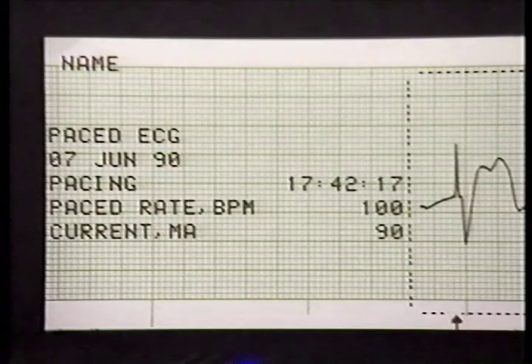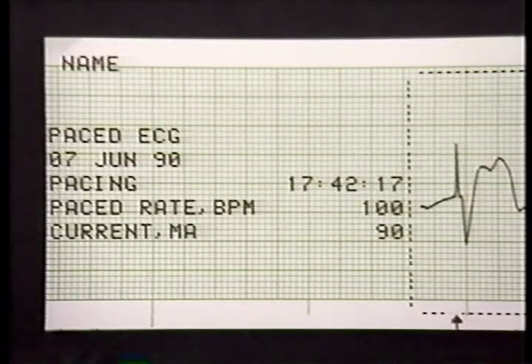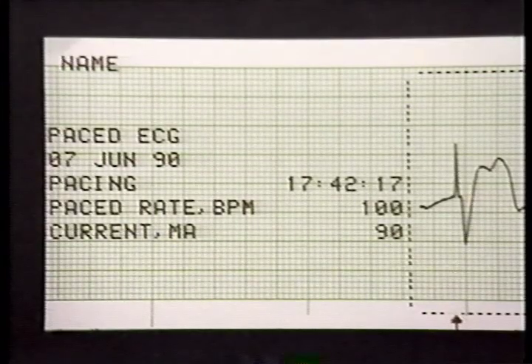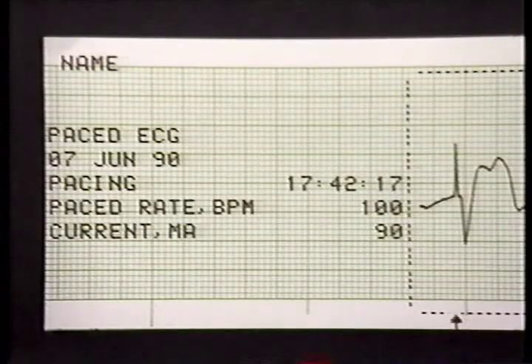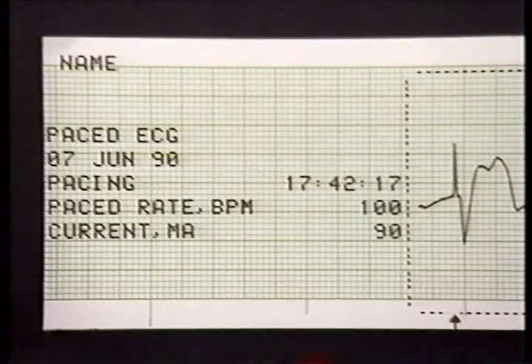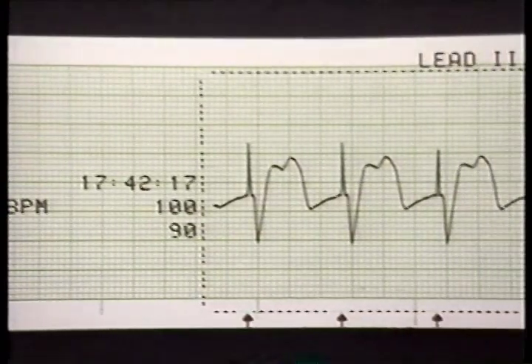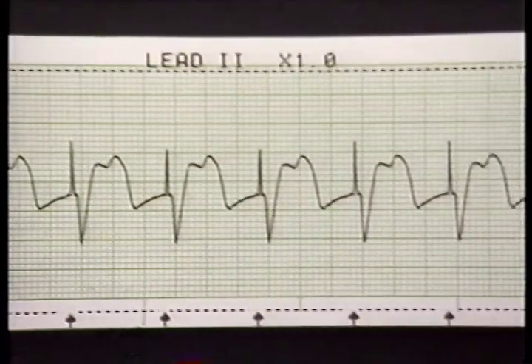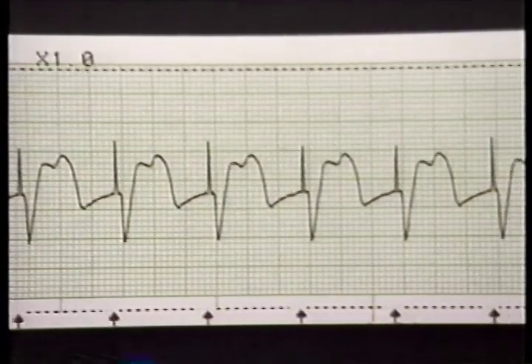The pacing format is printed each time pacing is initiated and the pacing controls are set for at least 10 seconds. If the pacing controls are changed after 10 seconds, another pacing ECG strip will be entered into Code Summary. The information preamble includes a space for the patient's name, a paced ECG label, the date, the time the pacer was activated or the controls were adjusted, pacing rate in beats per minute, and current in milliamps. Following the preamble are 6 seconds of pacing data with lead and gain settings. The arrows at the bottom mark each pacing stimulus.